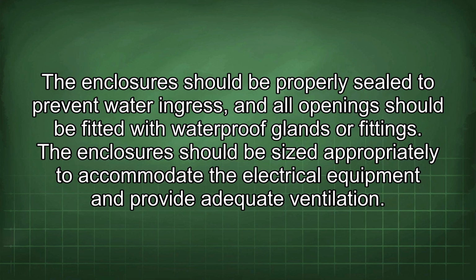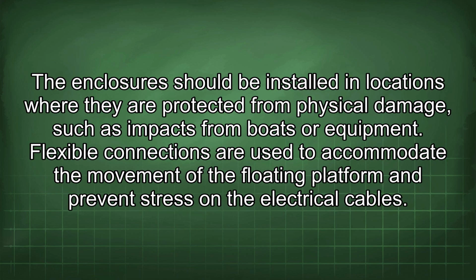The enclosures should be sized appropriately to accommodate the electrical equipment and provide adequate ventilation. The enclosures should be installed in locations where they are protected from physical damage, such as impacts from boats or equipment. Flexible connections are used to accommodate the movement of the floating platform and prevent stress on the electrical cables.